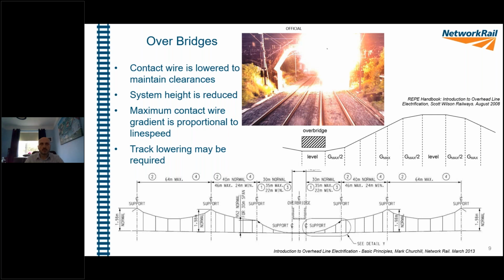So if we've got a steeply graded contact wire, the 90 newtons uplift force will be exceeded as the pantograph is moving towards the bridge as the contact wire reduces its height. The gradient I'm referring to of the contact wire has an impact on the wear of the pantograph on the overhead line system, and that reduces the actual line speed of the route in these areas. This can be particularly challenging where we have an overbridge and a level crossing in close proximity. So the overhead line height needs to go from the high level crossing height to clear vehicles to the low height throughout the bridge. So we have quite a steep gradient, and there are locations in the UK where line speed has been limited because of that.